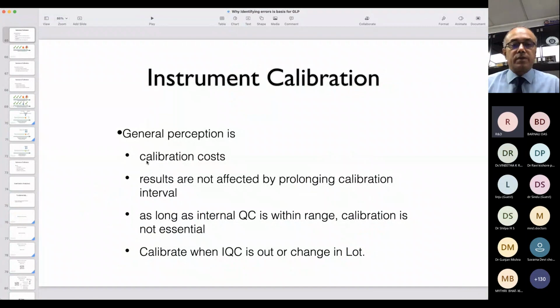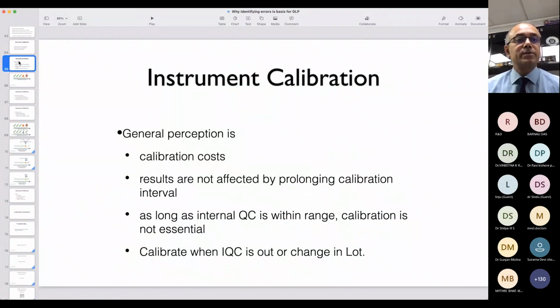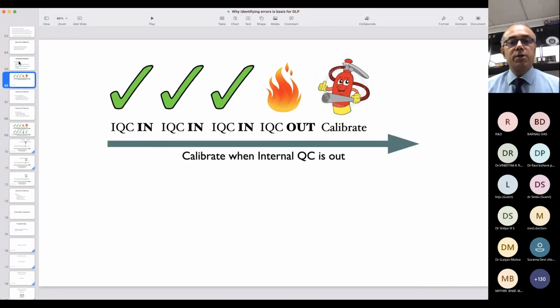Okay. So the general perception is that calibration costs, and there's a problem if we have to regularly calibrate. And I find that extremely challenging to explain, but I will try and do it in this slide. So the general perception is when QC is fine, let us not calibrate. So only when the QC goes out, we need to calibrate.